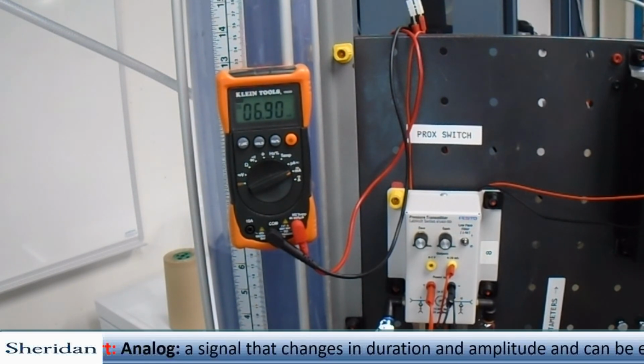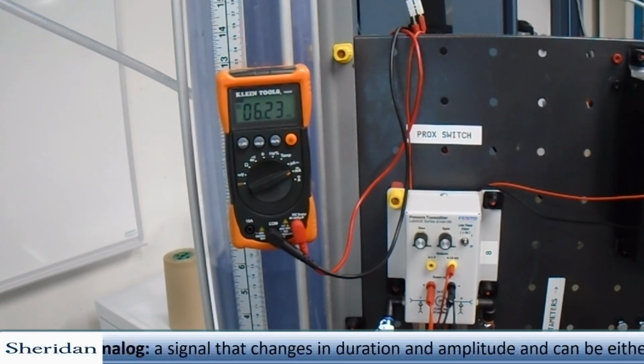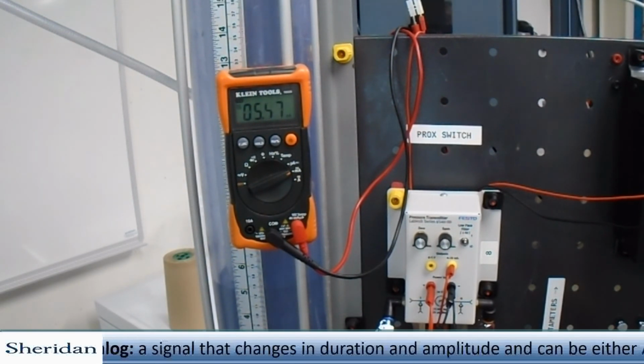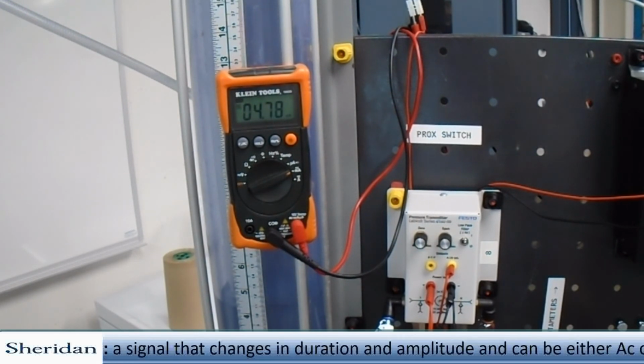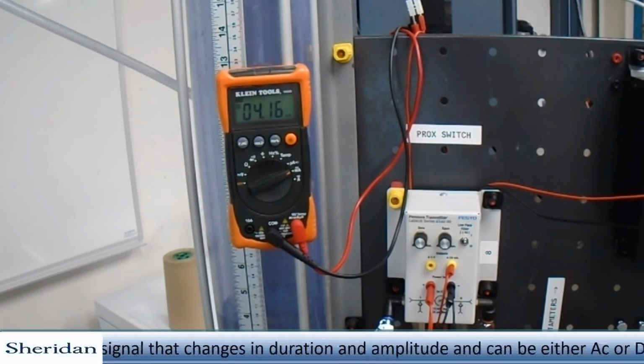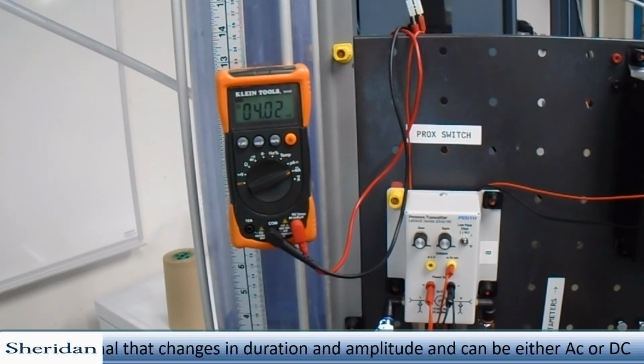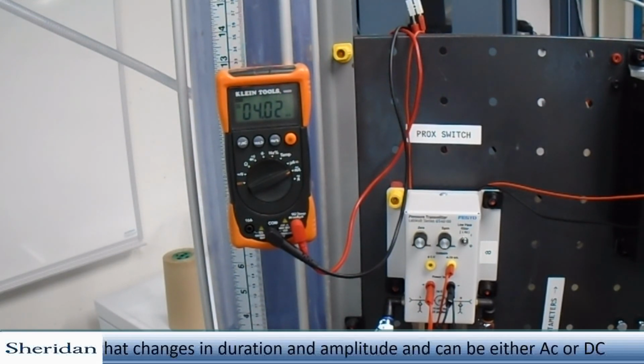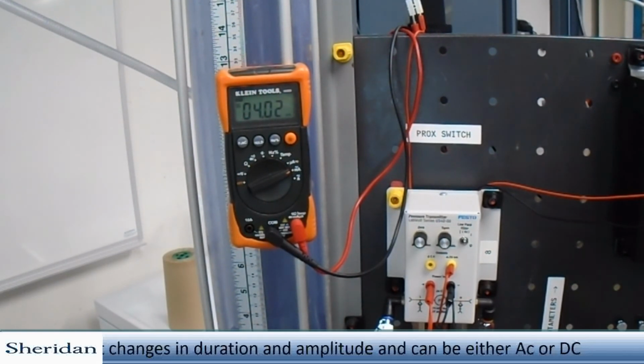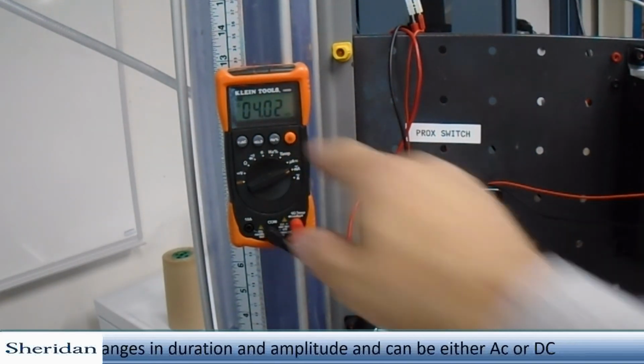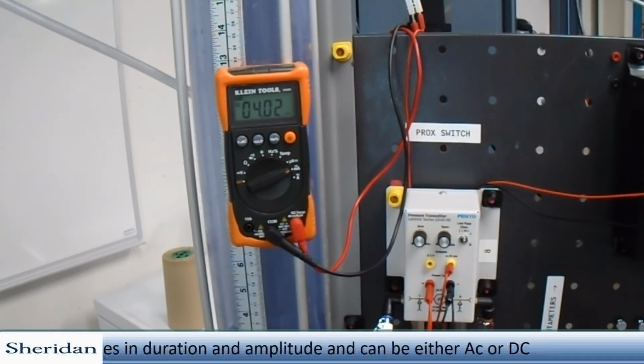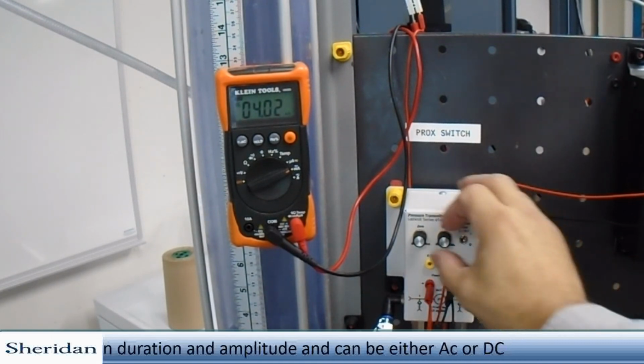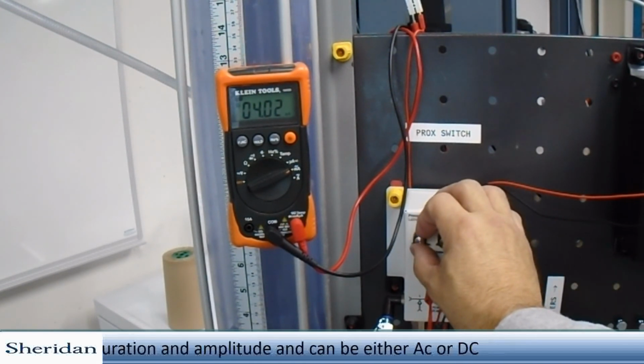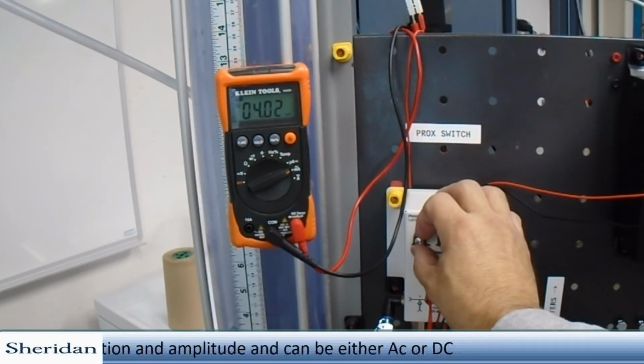Because we've adjusted our span, when we get to our zero, which is 2 inches, we should see that the number may not exactly be close because each one will affect the other. So we're at 3, 2.5, and 2. So at 2 inches of water column, my reading is at 4.02. So I'm going to try and get it down a little closer.